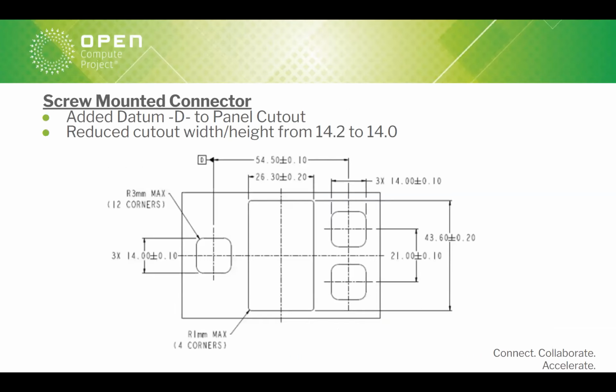Next slide. An additional change has been the addition of datum D. Datum D on this view ties to the overall spec, referenced in other specs and tied back to this spec as well as the IT gear. The 14.2 dimension from the previous spec has been updated to 14 plus or minus 0.1. This was to align to plus or minus 3mm float on the connector, since as previously dimensioned the float could exceed 3mm. So this was a tolerancing update to align to the float specs.